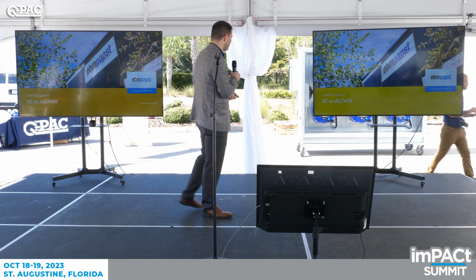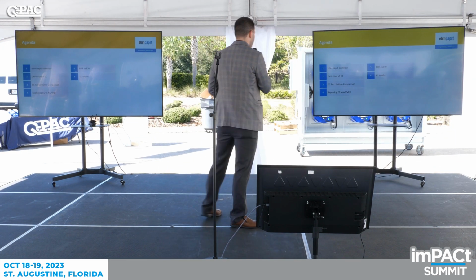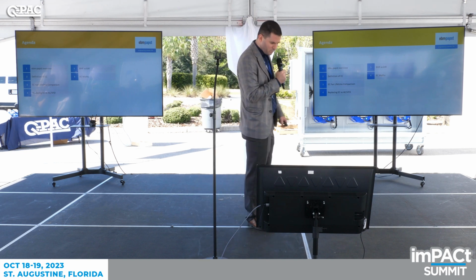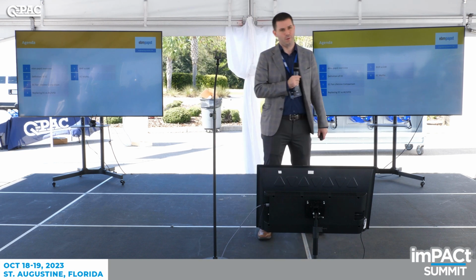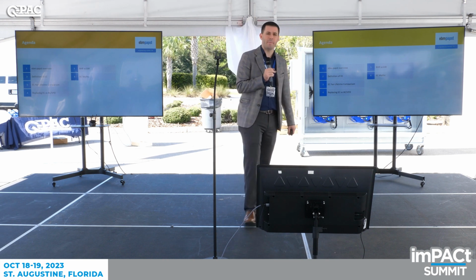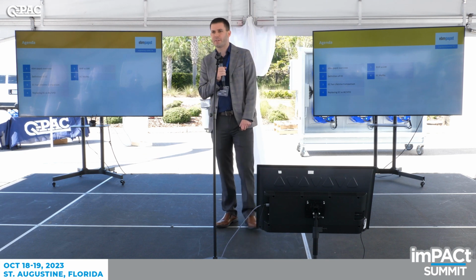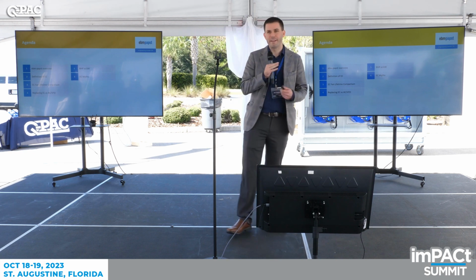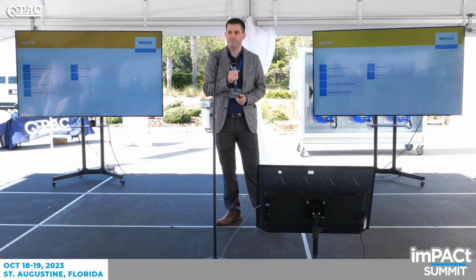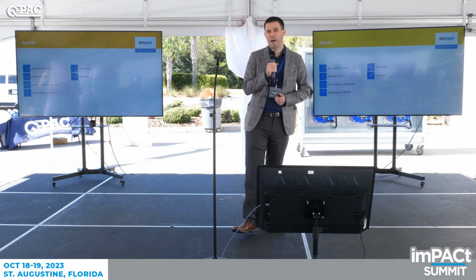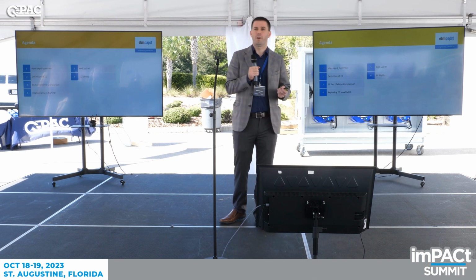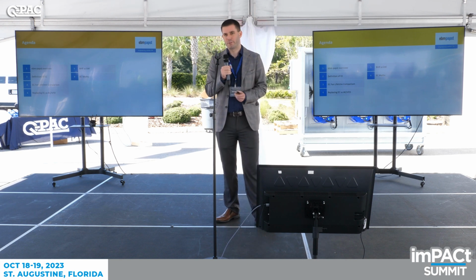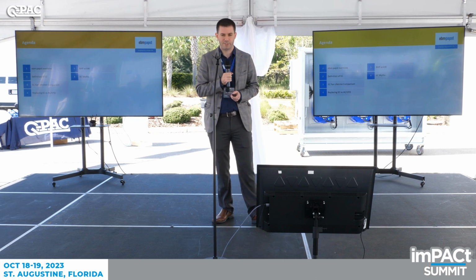All right, so, let's see. Okay, so this is what we're going to talk about today. Just a quick overview of who we are, one slide. Then we'll get into the definition of what an EC motor is. I'm going to compare the lifetime of an EC motor versus an AC motor and a VFD, replacing EC motors versus replacing AC VFD motors, brake horsepower versus kilowatt. EC motors always give you a kilowatt. AC motors are always going to give you a brake horsepower with the fan. So how do we compare and contrast those two, and then go through some EC myths.